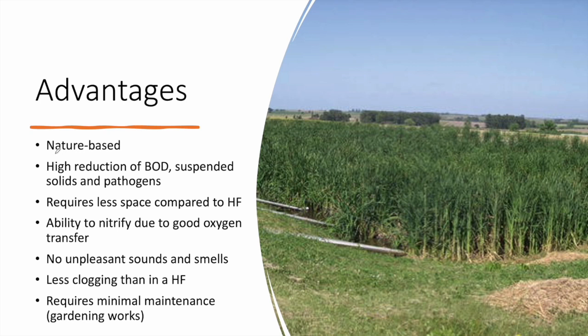Advantages of a vertical flow constructed wetland: it is nature-based with no major structural or mechanical equipment. It achieves high reduction of BOD, suspended solids, and pathogens compared to a horizontal flow wetland. It requires less space, has the ability to nitrify and reduce total nitrogen due to good oxygen transfer, produces no unpleasant sounds or smells, has less clogging than horizontal flow wetlands, and requires minimal maintenance — only some gardening work.